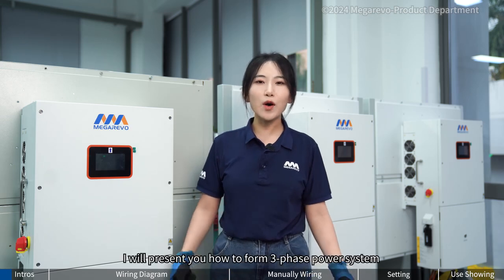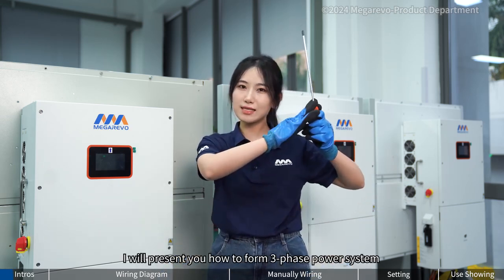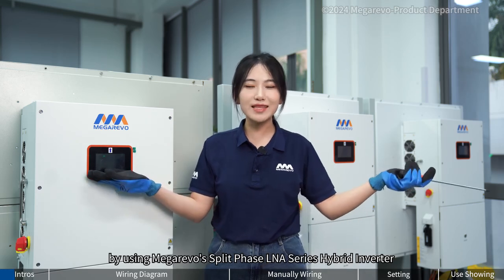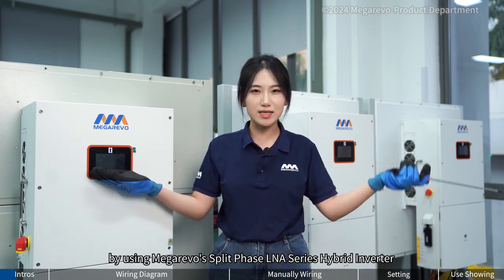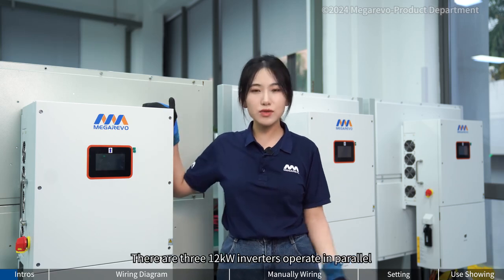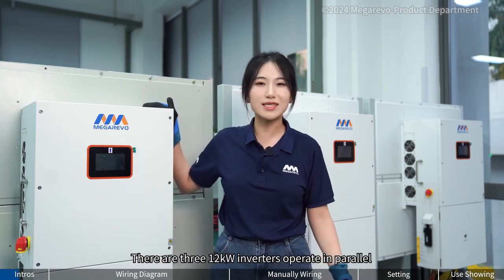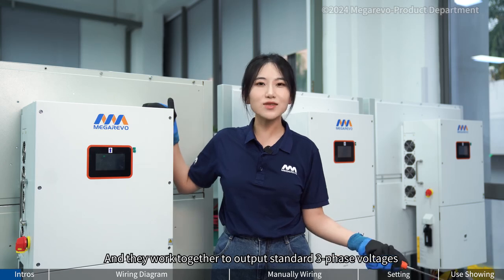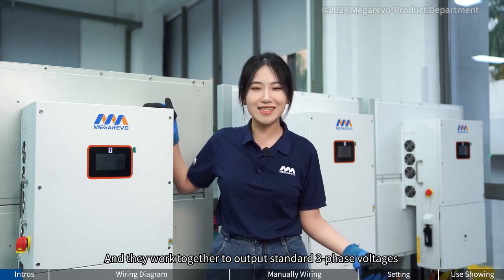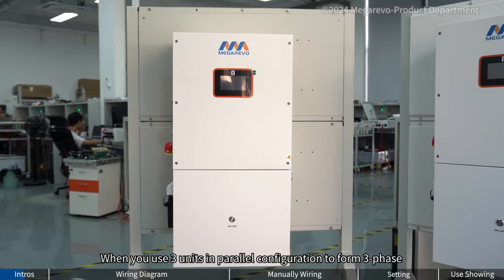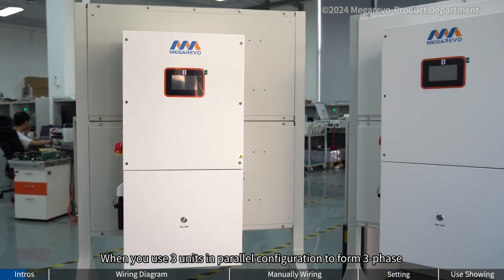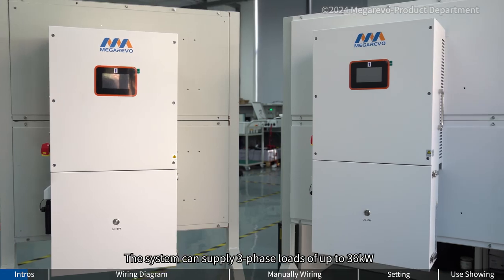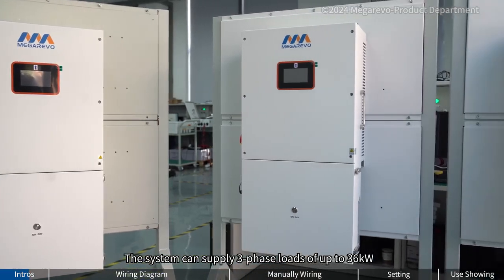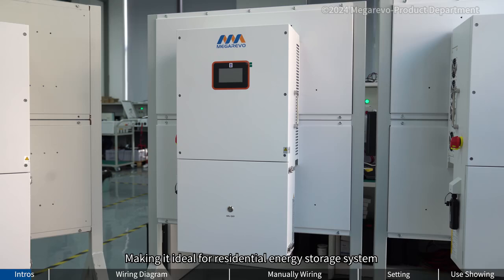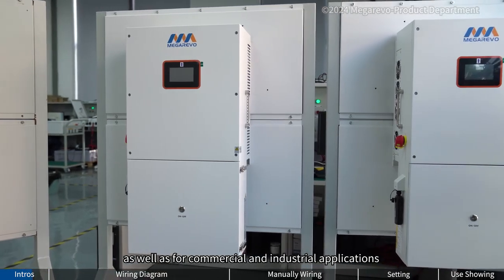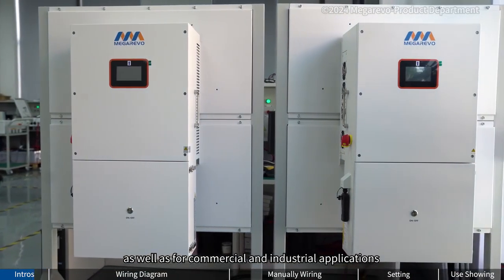Okay, in this video, I will present how to form a 3-phase system by using Megarevo's split-phase LNA series hybrid inverter. Behind me, there are three 12 kilowatt inverters operating in parallel, as they work together to output standard 3-phase voltages. When you use 3 units in parallel configuration to form 3-phase, the system can supply 3-phase loads of up to 36 kW, making it ideal for residential energy storage systems, as well as for commercial and industrial applications.